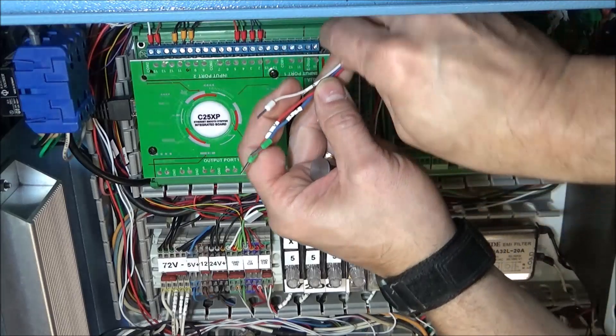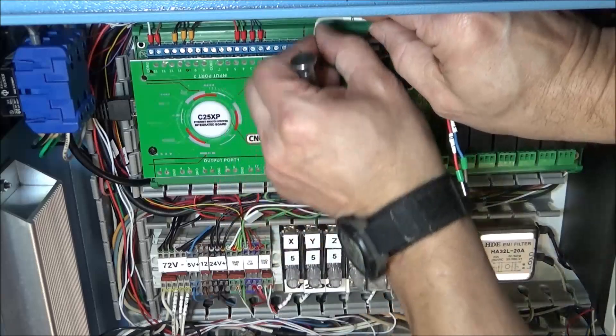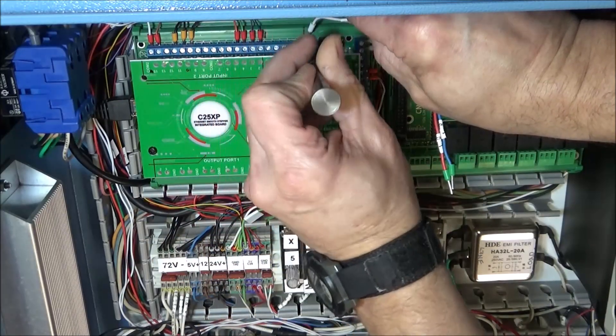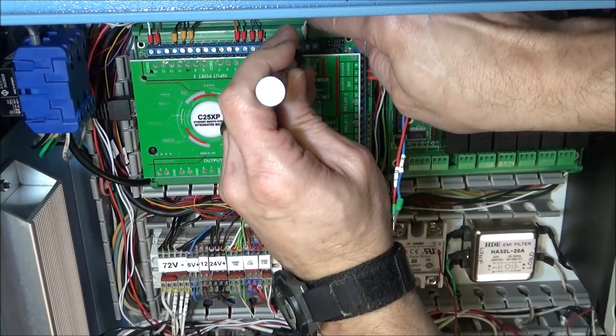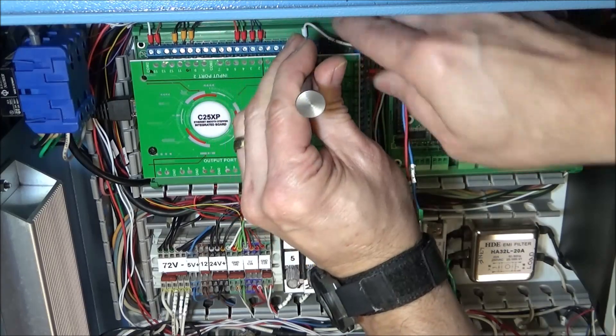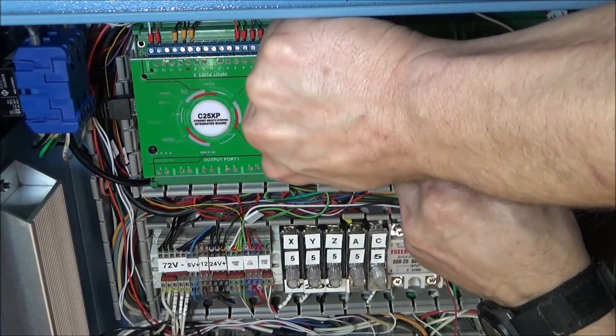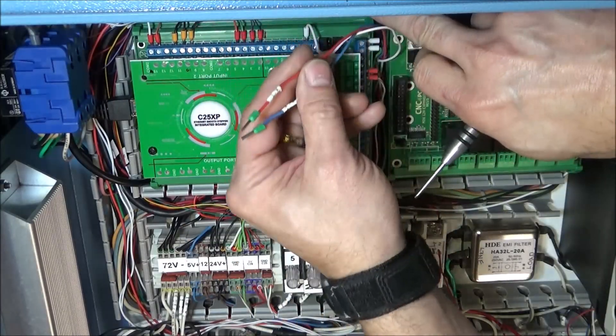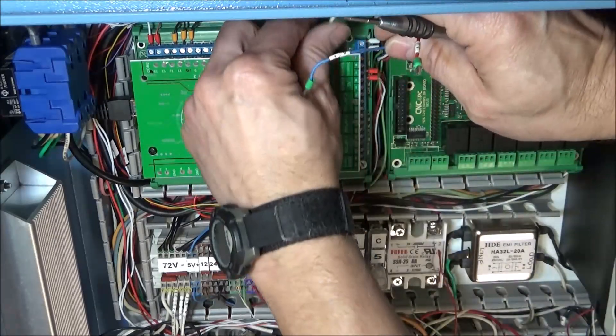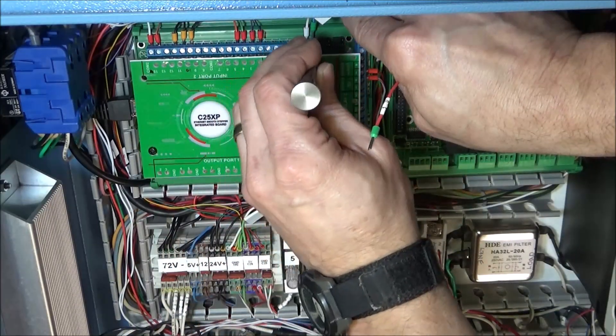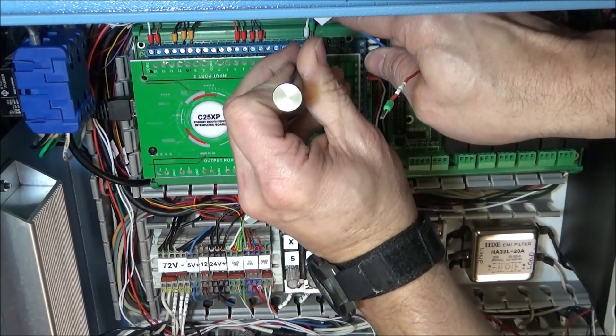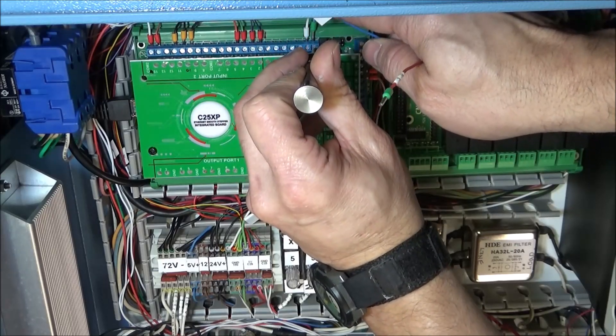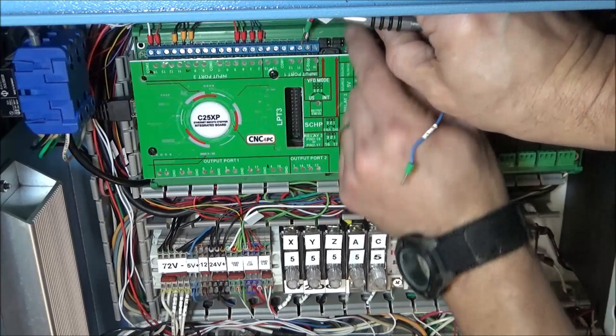Okay, then we have our e-stop white wire here—I've got it labeled e-stop—so that's going to go right here to the e-stop terminal that's on port 1. And then our next wire here is 10, and that's going to go to the other side of the e-stop here on number 10. Ten is typically the input number most people use for their e-stop, so Arturo just went ahead and made that. So this one is 10, the red one.